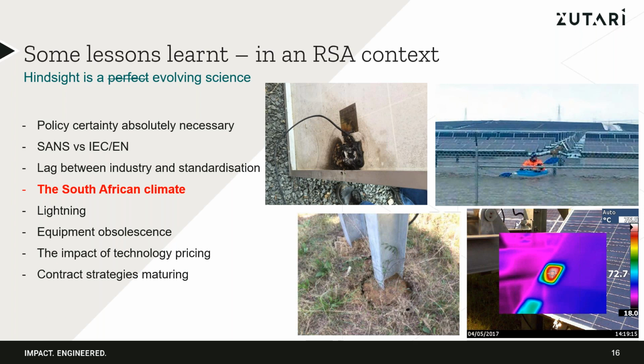In terms of equipment obsolescence, this is a very important aspect for solar PV, and unfortunately the reality is that I can't buy a PV module installed on a bid window 4 project. Say a 330 watt module from a manufacturer, I'd find it very hard to buy a number of those panels, because they're now obsolete and manufacturers no longer stock them - they've moved on to completely different modules. This hurts the DC side particularly, the PV modules and inverters. Those round 1 inverters are no longer stocked, and now to go and rectify 10 years in is quite an exercise in brownfield engineering.